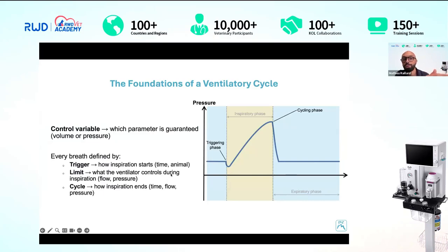Once I have decided the control variable, either pressure or volume, I also need to think about how a breath starts. A breath starts with a trigger, and the trigger could be time. I might decide that the animal will start an inspiration every 5 seconds, 10 seconds. But I could also say that the ventilator could help the animal when the animal wants to take a breath, and therefore the trigger could be an inspiration from the animal.